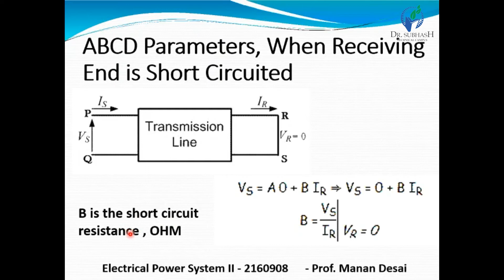Now this implies that applying the short circuit condition to the ABCD parameters, we get parameter B as the ratio of sending end voltage to short circuit current. When the receiving end of the ABCD parameter circuit is short circuited, VR is equal to 0, and so our equation Vs is equal to A into 0 plus B into IR. So ultimately Vs is equal to 0 plus BIR. So we got B, and B is a short circuit resistance and the unit is ohm.